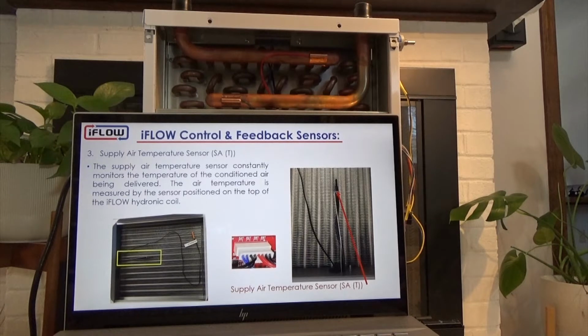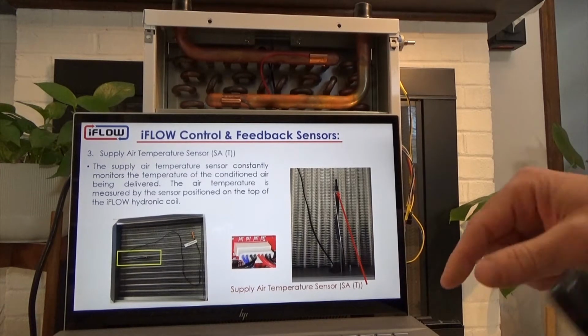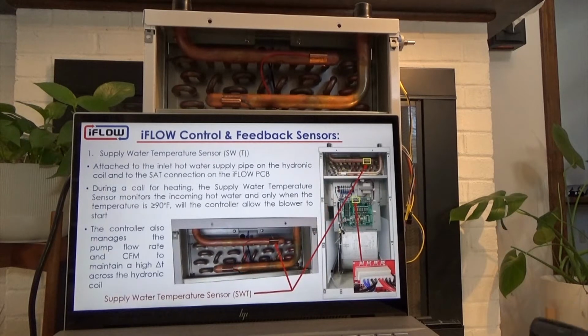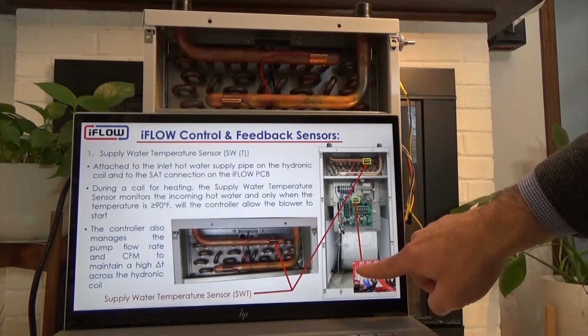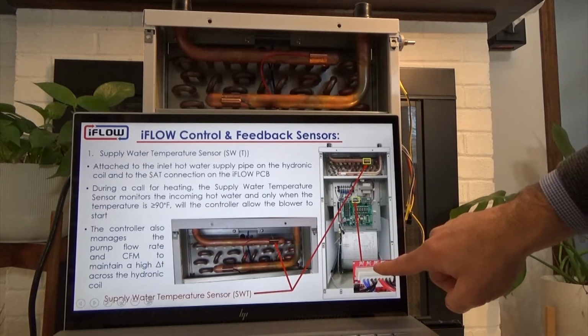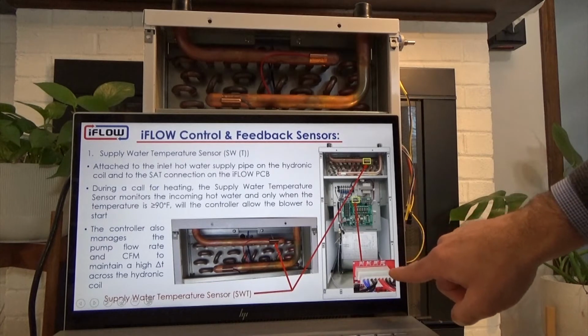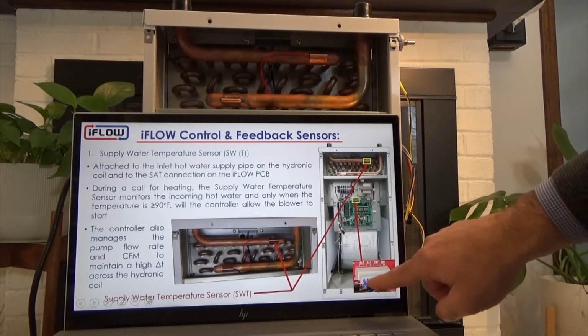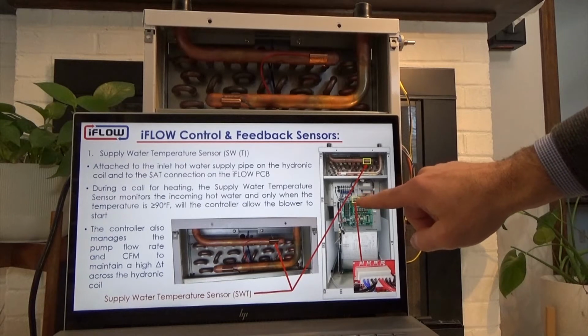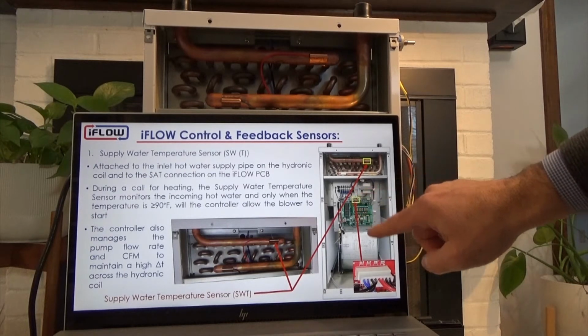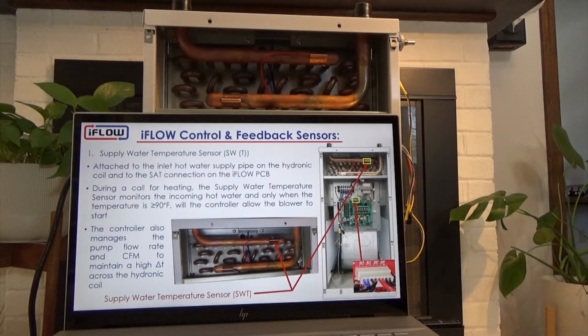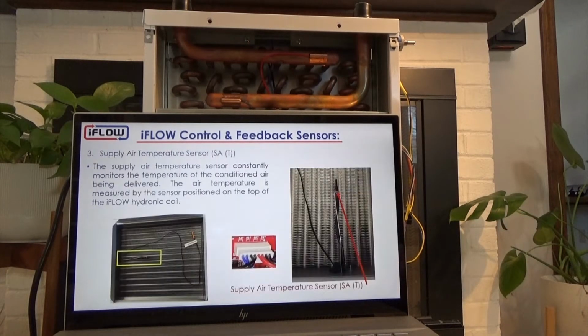Number 3 is the supply air temperature sensor. First of all, if we go back, the supply air temperature, the return air temperature, the supply water temperature, and the return water temperature all connect in one harness at the top center of the board usually, and you can see the various wiring in the display. So now we get to the supply air temperature.